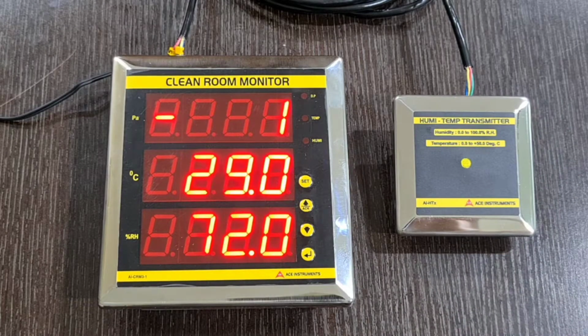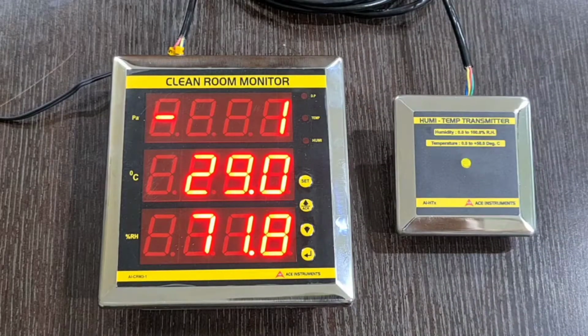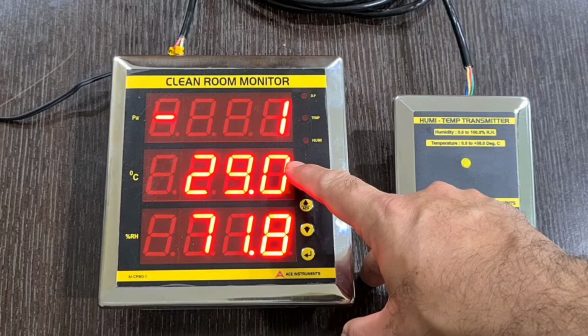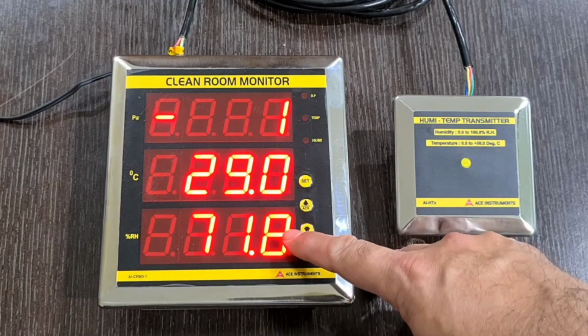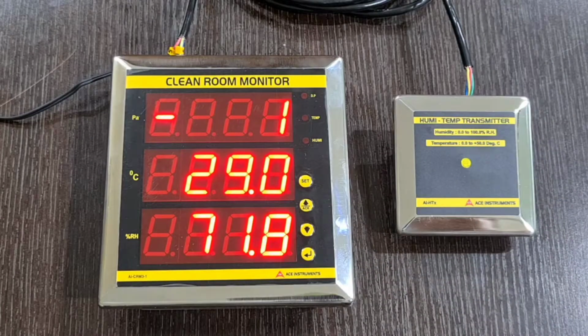The ACE Hospital Room Monitor measures differential pressure in customizable ranges like 0 to 50 pascals, 0 to 100 pascals, minus 100 to plus 100 pascals. Please pay attention here. The negative pressure for isolation rooms and also anterooms can easily be accommodated since the instrument is capable of measuring in negative pressures also. The other ranges being 0 to 1000 pascals. The instrument measures temperature from 0 to 60 degrees Celsius and humidity in the range of 0 to 100% relative humidity. The ACE Hospital Room Monitor has an integrated buzzer alarm.